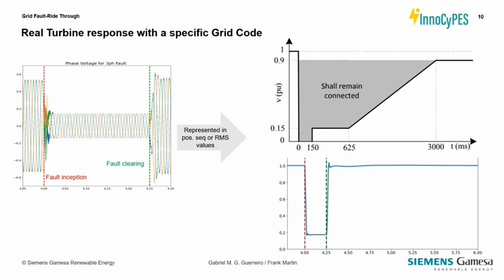This is an example of three-phase voltages. When a fault happens, the voltage will drop, and the turbine will identify the fault. You ride through the fault, and this is a very simple FRT curve from a grid code on how you should be connected. Within this gray zone, you should remain connected. That's basically what the grid code says, and each grid code tells you to do it in a different way. That's the big challenge, because as a manufacturer of a wind power plant, you need to fulfill different requirements on how you ride through faults and how you should behave during them.